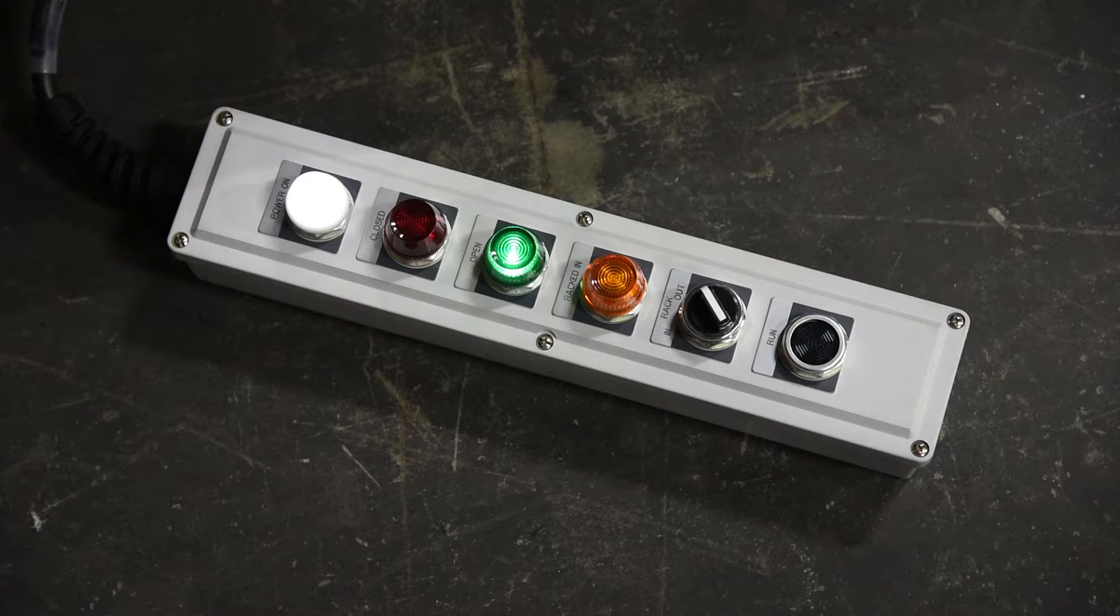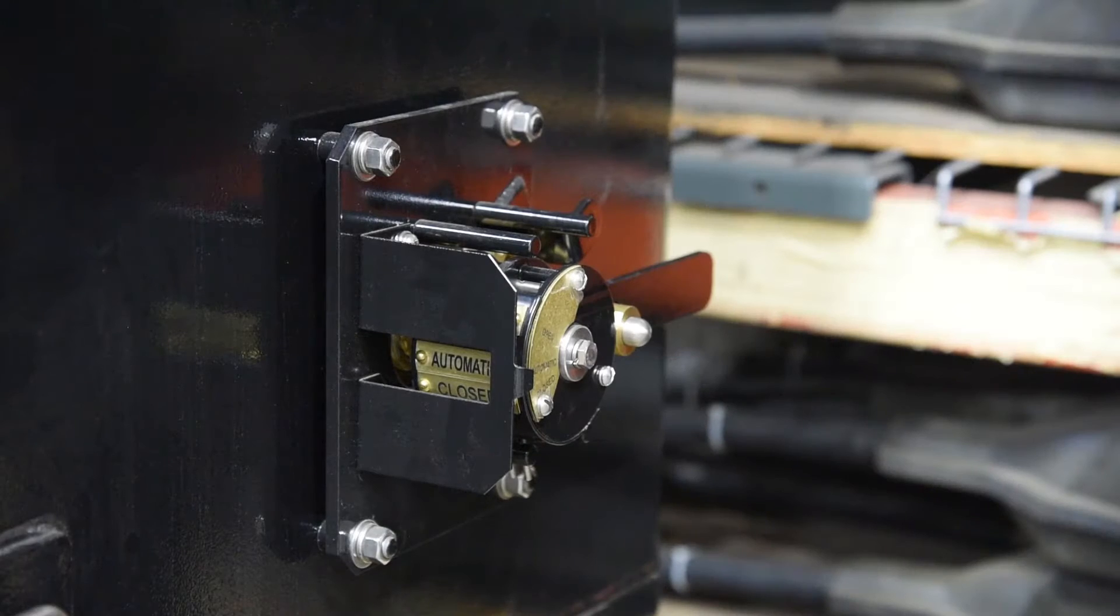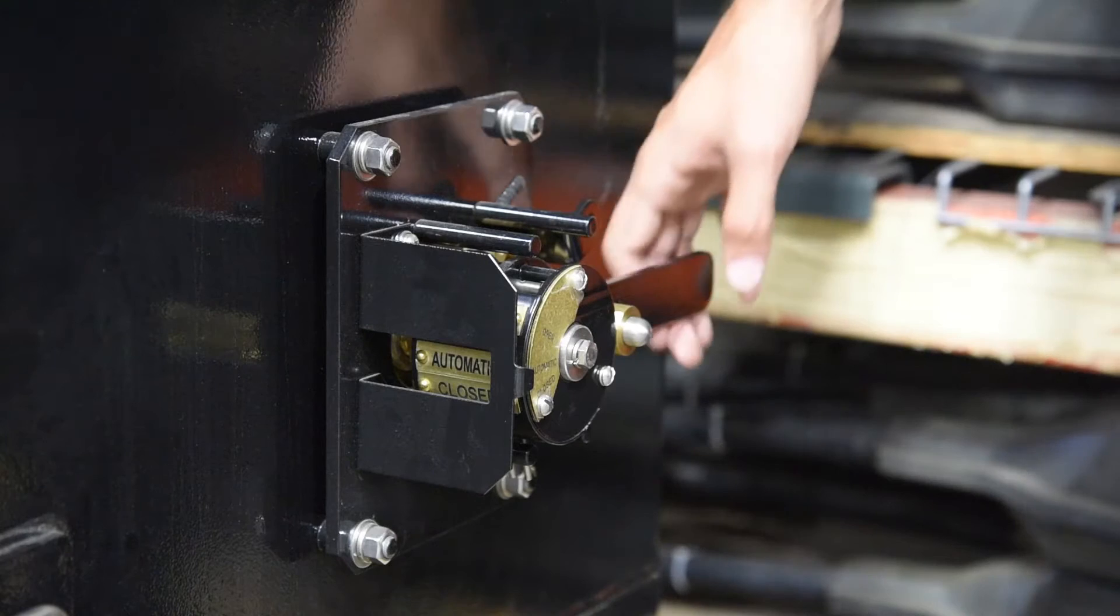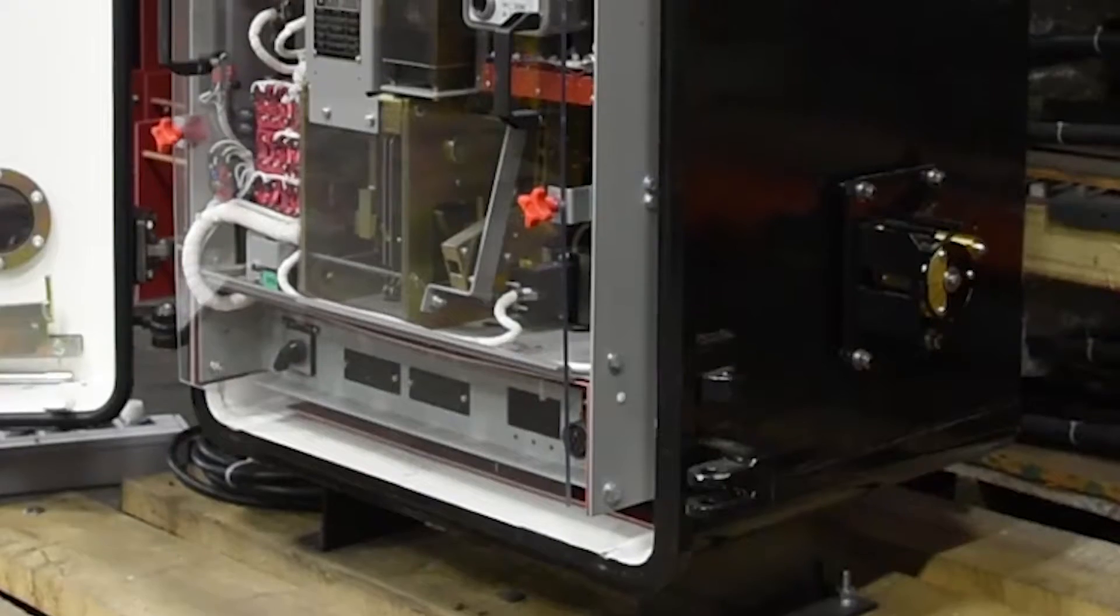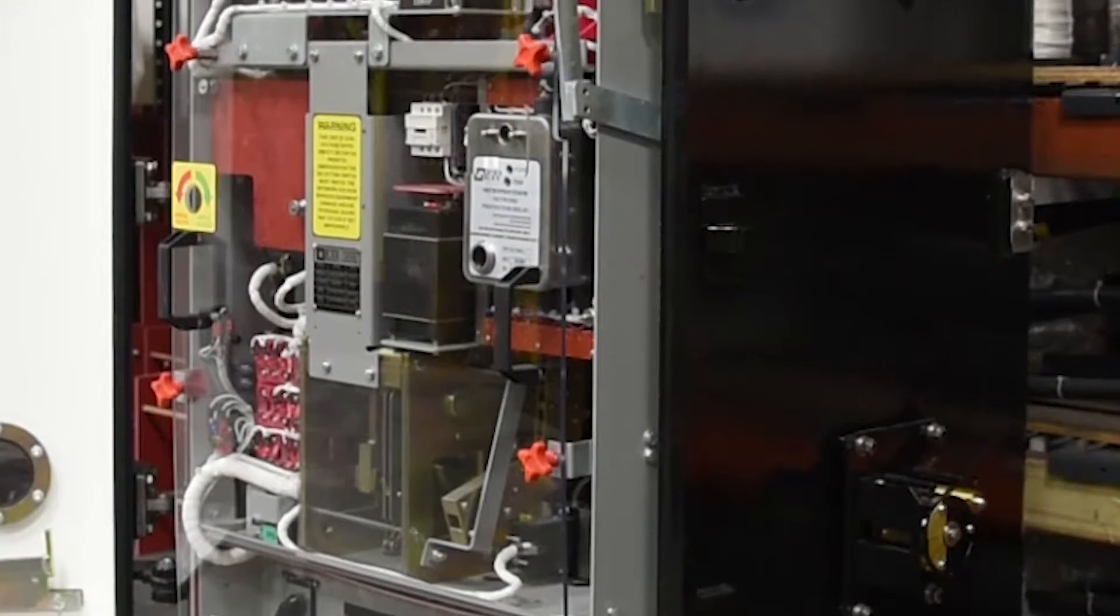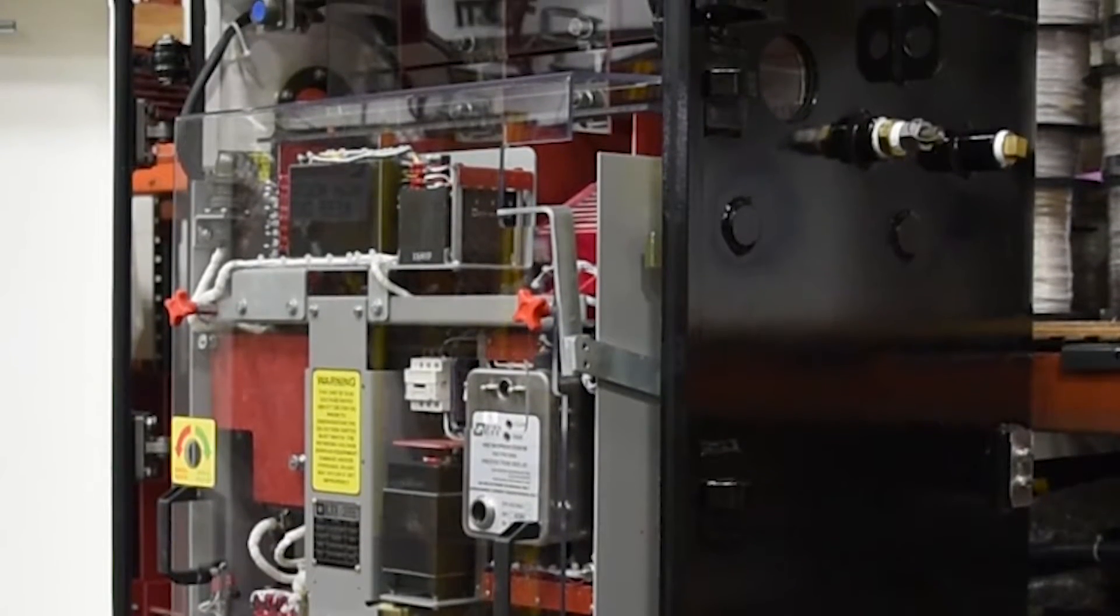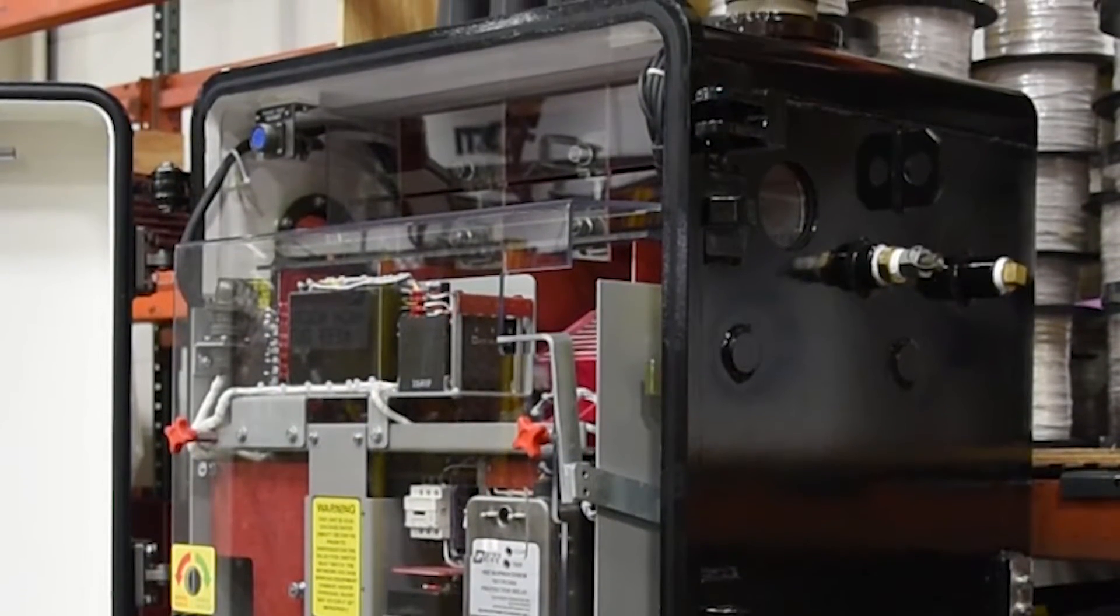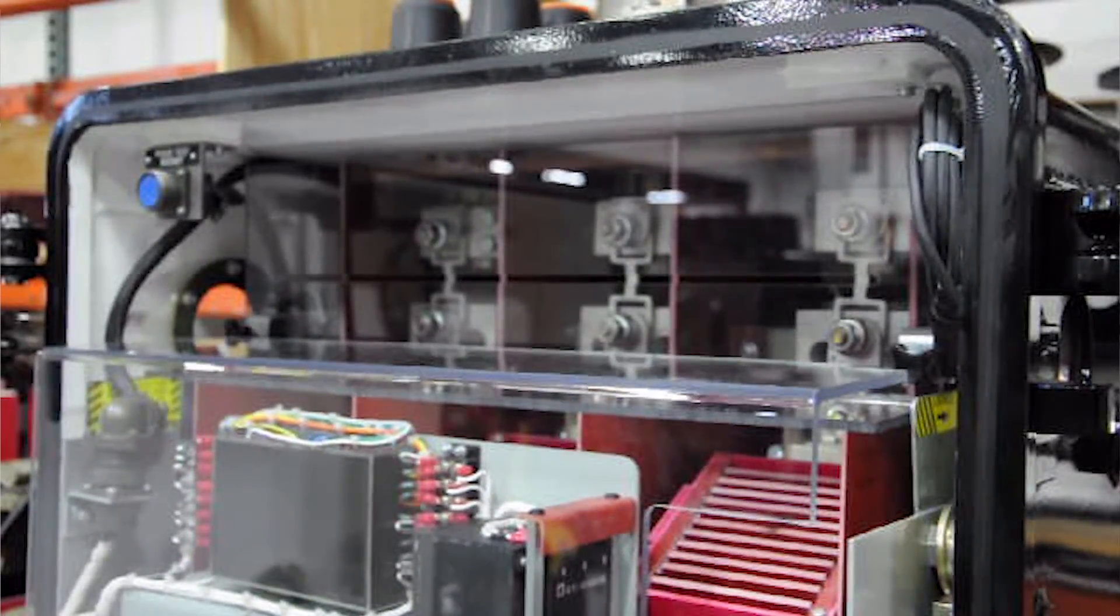The 416NP features electrical and mechanical interlocks to prevent the unit from racking in or out while under load. A limit switch requires the handle to be moved to the open position before the racking system can operate. The electrical interlock follows the B contact through the auxiliary switch preventing the user from racking the unit in or out with the network protector in the closed position. The racking system does not receive power without connecting the racking pendant.